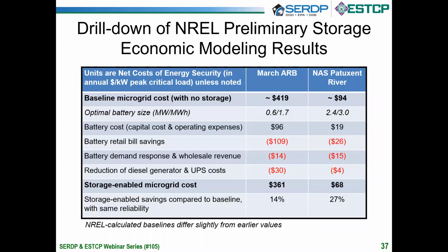Here, NREL breaks out the incremental costs and savings from adding battery systems to 2 of the installations: March with a small critical load and Patuxent River with a large critical load. I should mention that, like the investigator results, these are preliminary results, but well situated to review. First, you see the battery size that NREL's REopt model selected: 0.6 megawatts of power and 1.7 megawatt hours for March, and 2.4 megawatts of power and 3 megawatt hours of energy at Patuxent River. You can see that in italics in the second row down. That is the optimal battery size row.